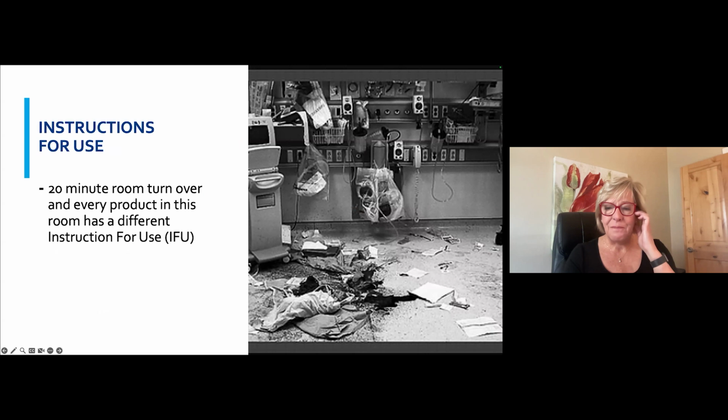So I'm going to just touch on this. Sarah's going to talk more about instructions for use. Oftentimes, people don't understand that in the United States right now, the Joint Commission has said they are going to enforce instructions for use. That has always existed, but they're getting much more firm about that issue. What people don't understand is that manufacturers create instructions for use for every single product that is in the environment, and they are not the same.